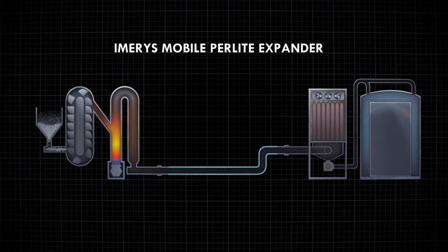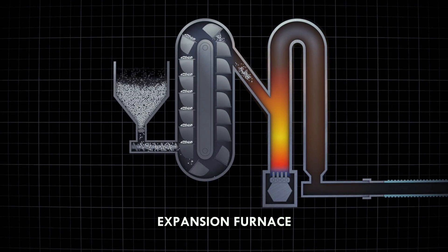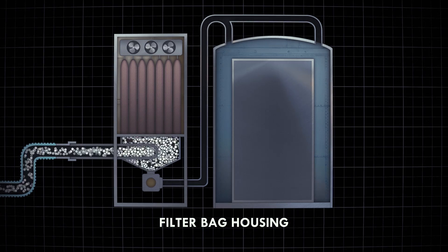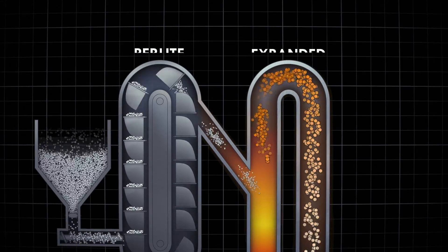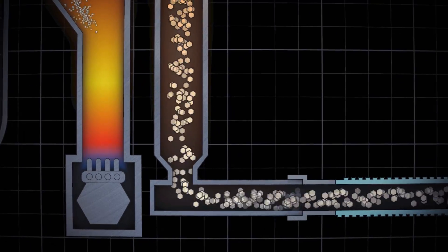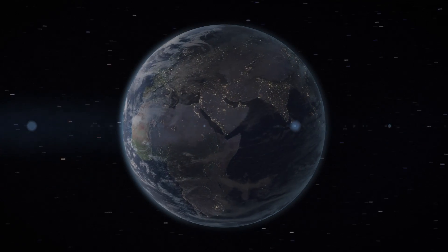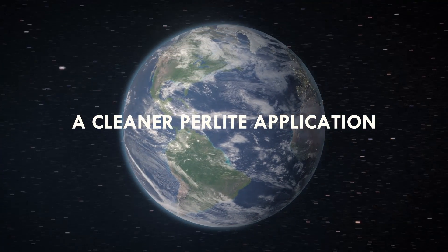Once the mobile expander is on-site, the Imerys team expands the perlite ore and conveys it through a series of pneumatic tubes into the void spaces. Our portable expander plant uses a negative draft system equipped with a filter house under negative pressure, preventing perlite from leaking into the atmosphere. Superheating the water particles trapped inside the perlite causes the ore to pop and expand, as powerful vacuums pull the expanded perlite through a long cooling tube to the filter bag housing, where it is pumped into your tank's annular spaces.